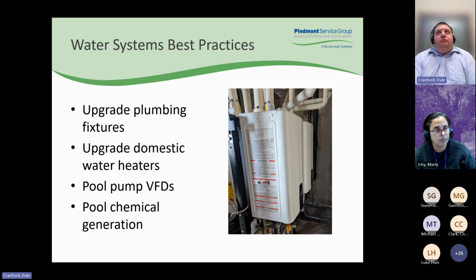One unique energy conservation measure we implemented as one of our recent performance contracts was pool chemical generation. So instead of buying chlorine, they use a salt generator on site to generate chlorine, and that significantly reduces operational costs from the reduced cost of the salt versus the chlorine. There's a little bit of an energy penalty of generating chlorine on site, but there's additional energy benefit because in a lot of cases you have to do additional water dilution if you're using purchased chlorine. And so there's some energy benefit and some water benefit on that side.